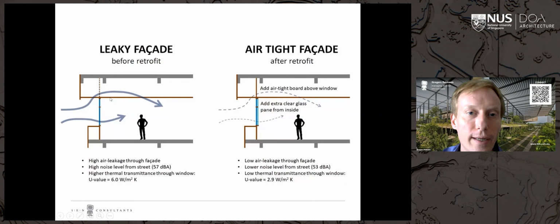What we also found when we removed some of the suspended ceiling panels was that there was no separation, no wall here. So what separated the aircon space from the outdoors was just these suspended ceiling panels and outdoor panels above the exterior windowsill. This was an open return aircon system, meaning the aircon air, when pulled back to the air handling unit, passed through this ceiling space and was not ducted. So this space up here was also air conditioned, which was not ideal. I'm sure we lost quite a lot of cooling that way.